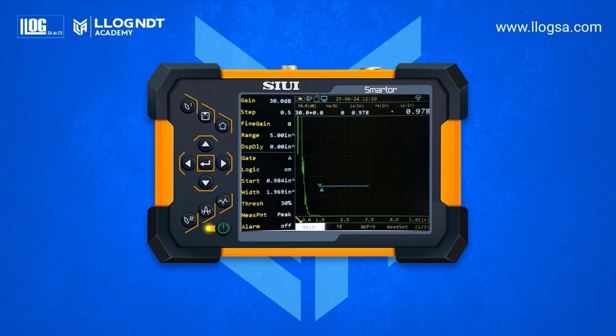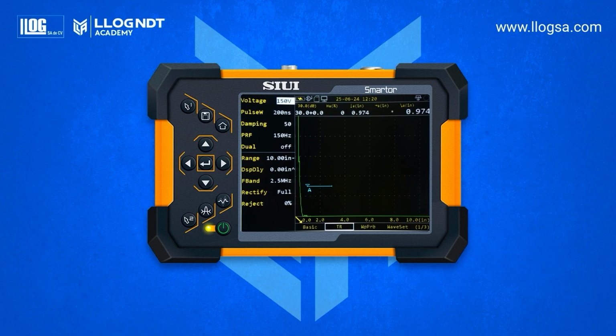We will now perform the preliminary setup and calibration using an angle beam. In the Basic submenu, we make the following adjustments. Gain step, 0.5 decibels. Display range, 10 inches. Display delay, 0. Gate measurement mode, peak. In the transmitter-receiver submenu, we configure voltage, 150 volts. Damping, 50 ohms. Pulse repetition frequency, 150 Hz. Dual mode, off.